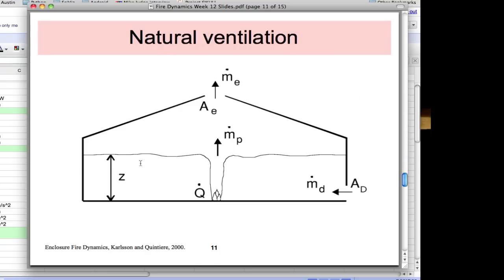Once we can determine smoke filling, how do we manage that smoke? Natural ventilation can be used where we have a fire filling up an enclosure, a mass flow rate from the plume, and area for mass flow out through a vent, plus supply air through a door. A fire alarm system or temperature-activated vents can open roof vents. With this method you can calculate what the steady-state smoke layer height would be, since you now have both filling and mass loss from the hot gas layer.